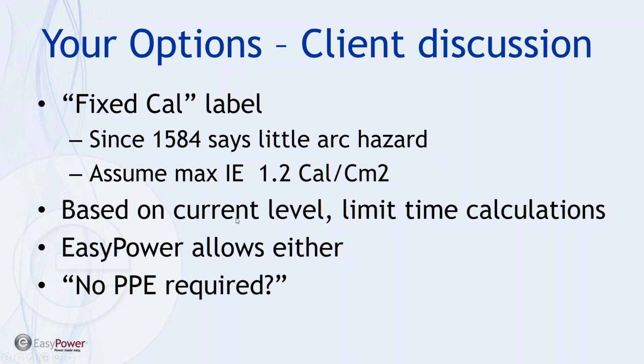Now, on the other hand, we might want to go in and, so here we're talking about a fixed energy level. Another alternative is to limit the calculation time so that it produces a calculated result inside or near this appropriate level. Now, in either case, we're talking about doing something rather than just letting the tool, the model, calculate the results. And that's why we suggest, and IEEE reinforces, that sound engineering judgment needs to prevail. So let me just show you how this works in EasyPower.